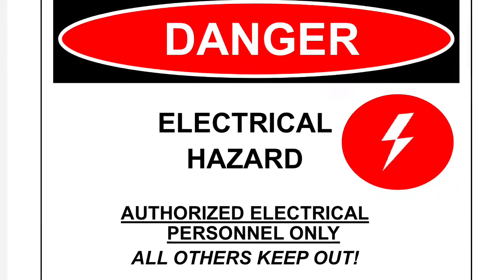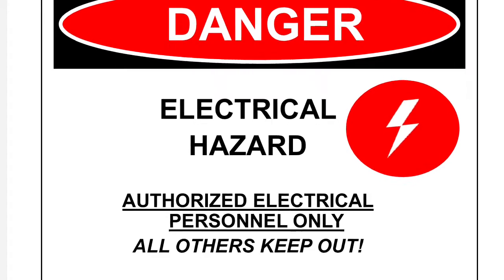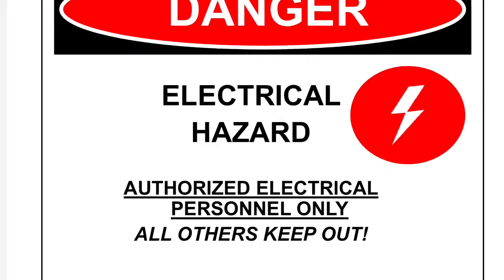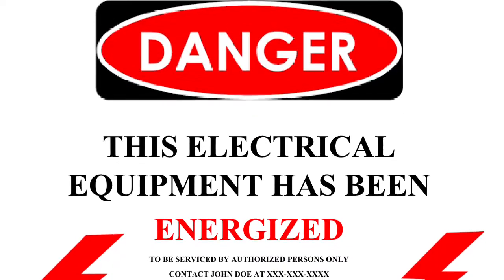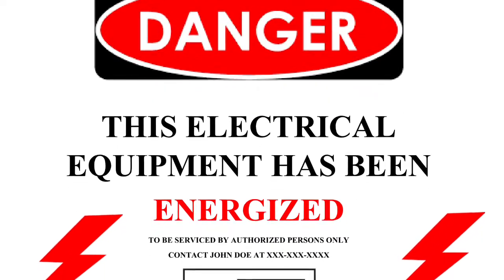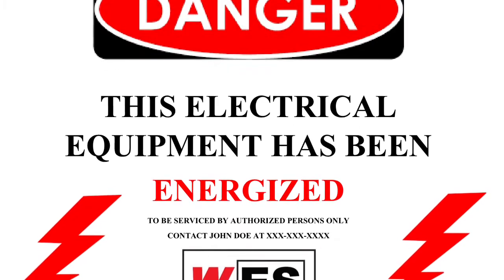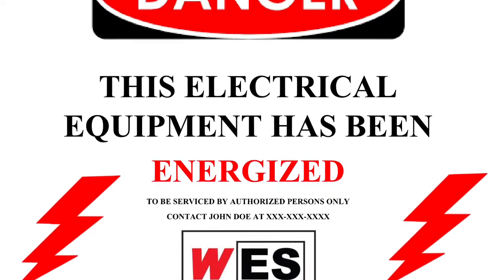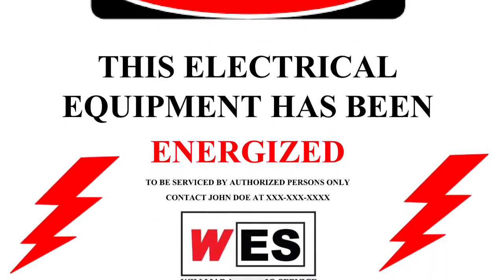Entrances to areas with live electrical parts must be marked with warning signs. Signs should forbid entrance except by qualified persons. At Willmar Electric Service, foremen have laminated energized equipment sheets that are applied to the fronts of panels and equipment after they are energized. The laminated sheets have the foreman's name and phone number on them.